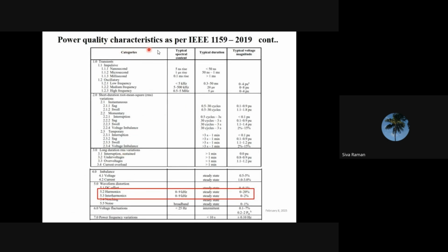So this is the table given in IEEE 1159. In transient, there are two types: impulsive transient and oscillatory transient. And in the short duration voltage variation, there are instantaneous, momentary, and temporary categories, with voltage sag, swell, and interruption parameters. The corresponding duration and magnitude are given on the right side. For example, it will be called an instantaneous sag if it happens between 0.5 cycle and 30 cycles, with an RMS voltage reduction between 0.9 and 0.1 per unit of voltage.